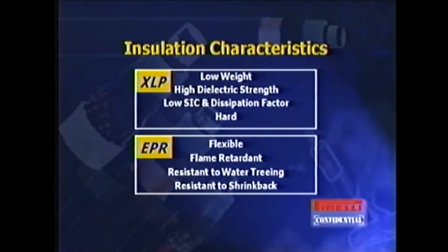EPR, on the other hand, some of its benefits are that it's very flexible as compared to cross-linked polyethylene, meaning that in installations where you have large conductors or maybe tight bends, EPR might be a better choice. It's also inherently flame retardant, or at least more flame retardant than cross-linked polyethylene. So where you have CT-rated designs, you might see EPR insulation systems. EPR is also inherently resistant to water treeing, making it ideal for submarine applications and any applications where you have extremely wet environments.